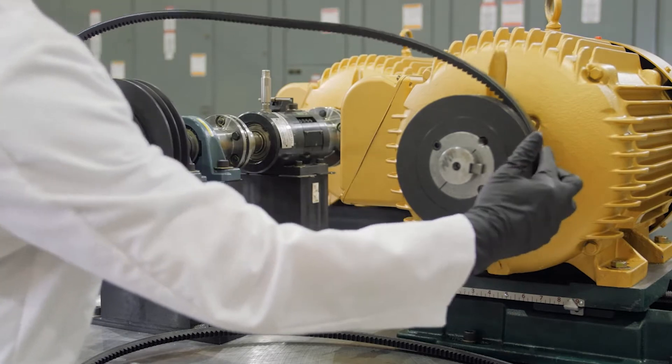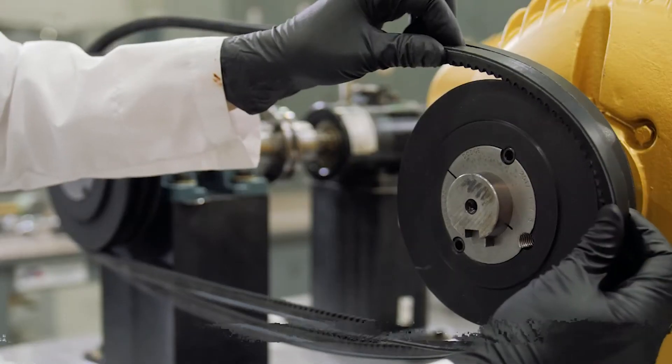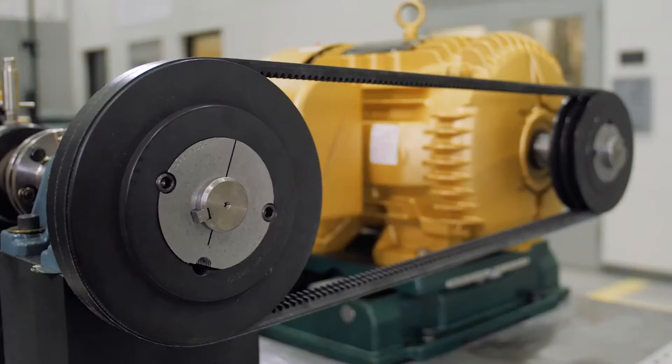Adjust the center distance as needed so that the belts can be loosely installed in the sheaves, and then adjust the center distance outwards to the approximate final distance.